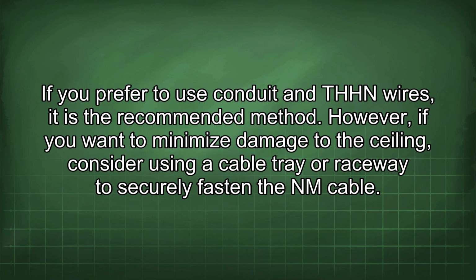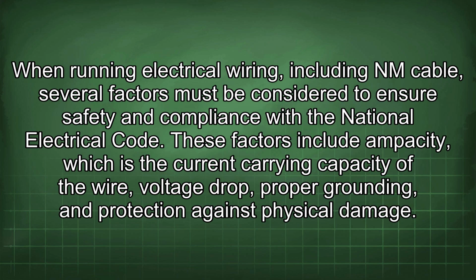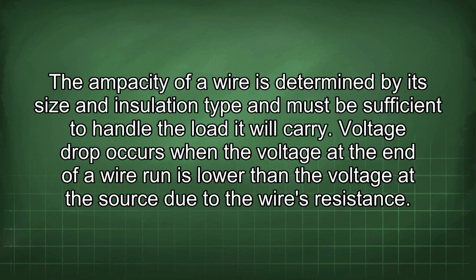When running electrical wiring, including NM cable, several factors must be considered to ensure safety and compliance with the National Electrical Code. These factors include ampacity, which is the current carrying capacity of the wire, voltage drop, proper grounding, and protection against physical damage. The ampacity of a wire is determined by its size and insulation type and must be sufficient to handle the load it will carry.